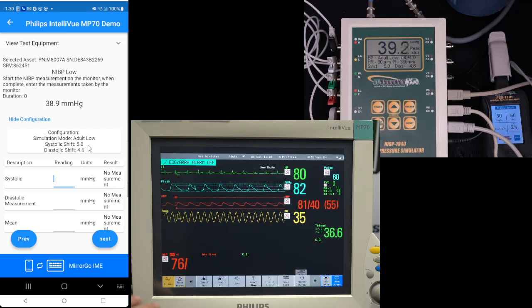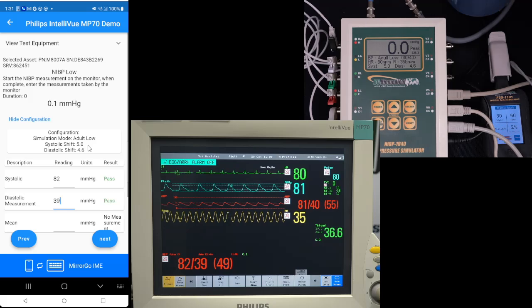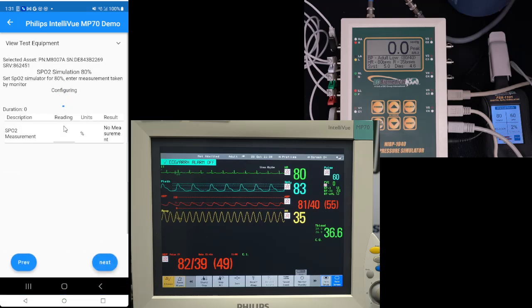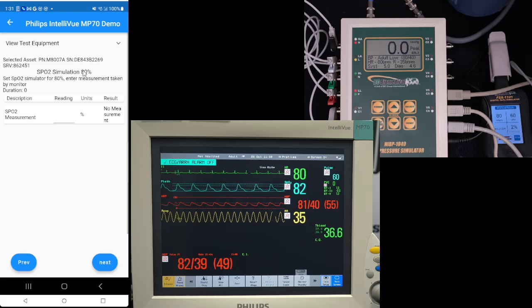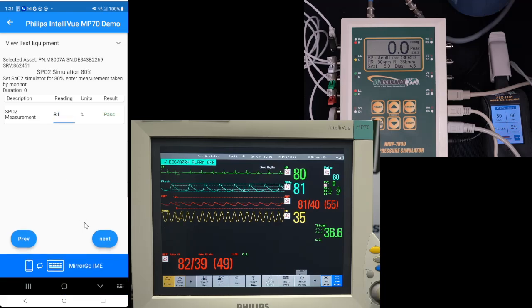And some monitors increase the pressure and then drop it and take measurements as the pressure drops. Some monitors take a reading as the pressure rises, so it just goes up once, and the NIBP series is compatible with either method of measurement from the monitor. Oops, 49. There we go. Okay, so that's all of our non-invasive blood pressure. So we want 80% SpO2. It's set to 80, and we got a reading of 81. So that's good. That passes.